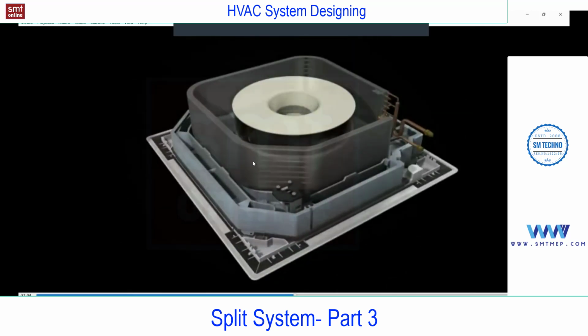You see, you'll find this evaporator coil. On the evaporator coil, condensation will happen, so water is going to be collected at the bottom, and this bottom we can call the drain tray. You'll find the passage for collection of water. But the important point is that, unlike the high wall, we cannot connect the drain pipe freely because this is going to be installed in the ceiling. In the high wall, it is going to be on the wall, so through wall chipping we can take the drain pipe below the level of that unit so that we maintain gravity to throw the drain water out through this U-trap. But in this case, I cannot take the pipe below the level of this unit because it is ceiling suspended.